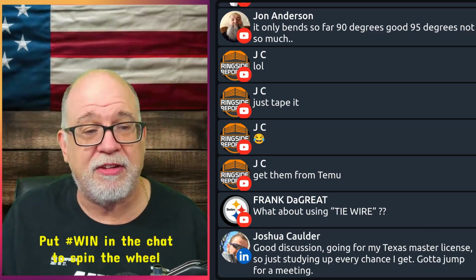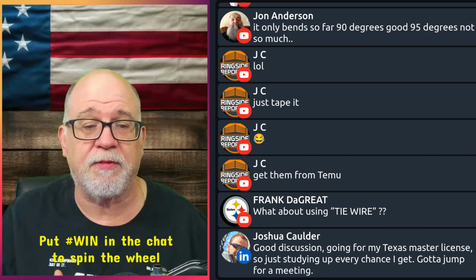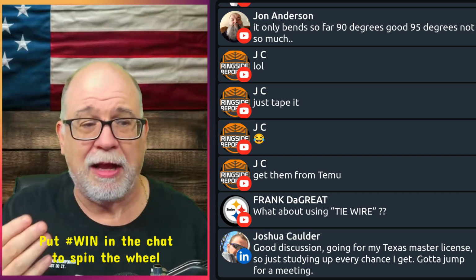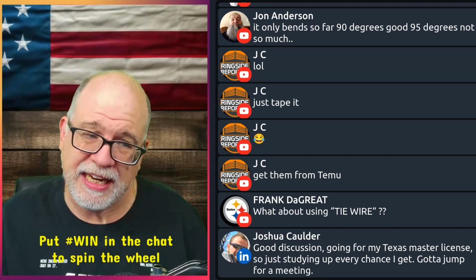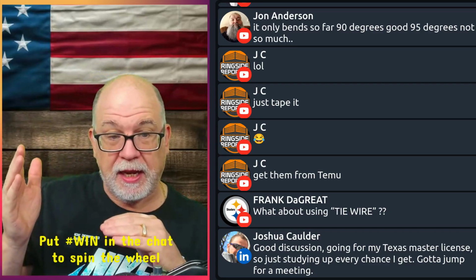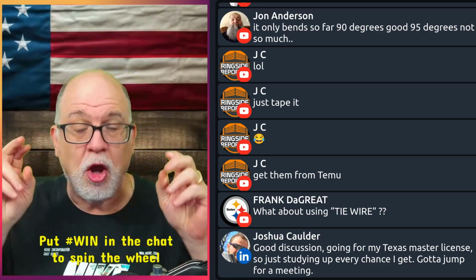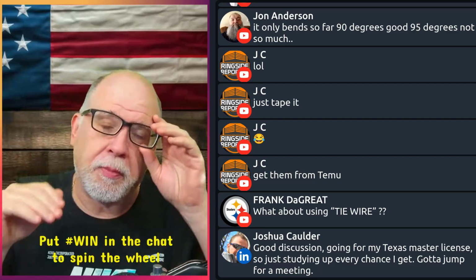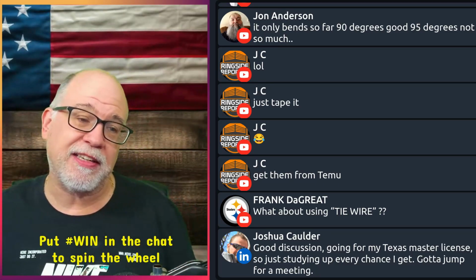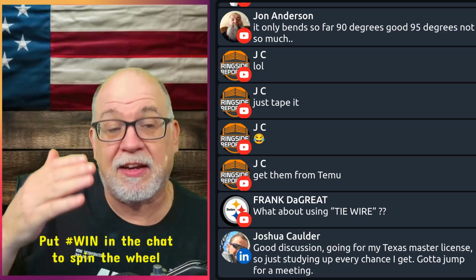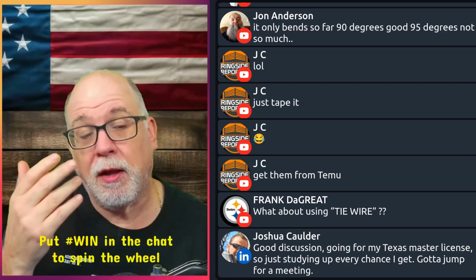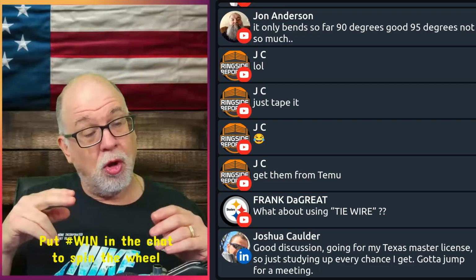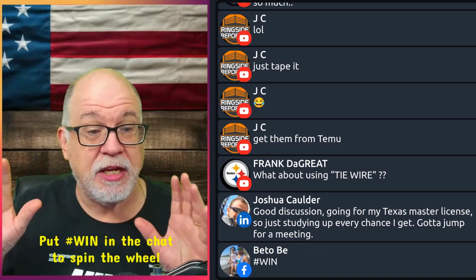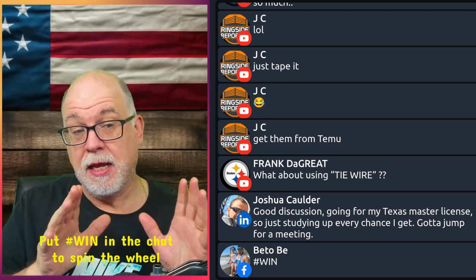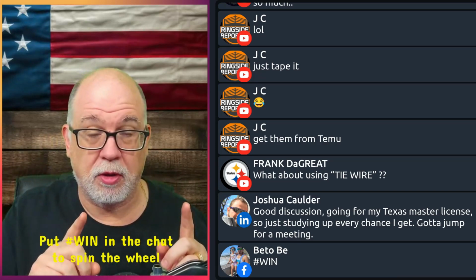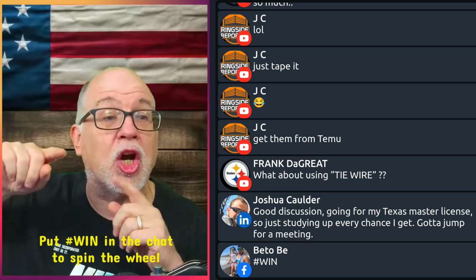So maybe you go to your AHJ and say, look, I'd like to submit for a modification or an amendment. And they go, well, what's your grounds for this? Show them the 2023 NEC, how we've progressed, and see if they will give you a variance on that one application. And there is a probability that they may. I used to give them all the time in the city of Richmond when people would come to me with the next edition, and I would look at it and go, well, the code's going to allow this anyway. I know you're not under the 2023. I know that you're under the 2020, but I will let you do this, okay? Because I know that is where we're going in the next cycle.